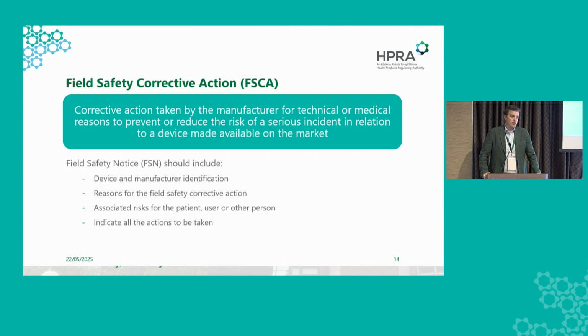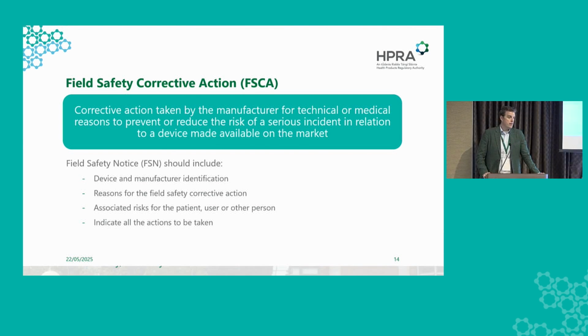So there's a distinction here between a corrective action that's taken at the manufacturing site, such as improving quality control or something like that, and an action that they take for a device on the market, which could be recall of the device, modification of the device, advice on how the device is used, or informing of a look back of previous diagnostic results. And again, field safety corrective actions are legally required to be reported to us in the HPRA if they affect the Irish market.